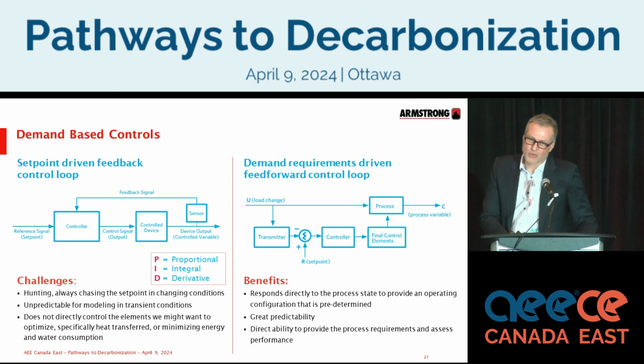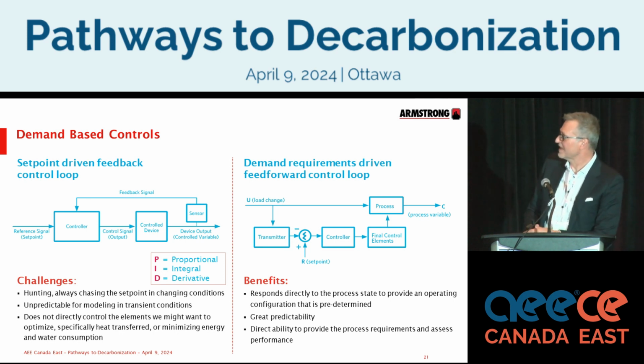Now, how are the controls done? Fundamentally, we are moving away from set point control, PID loops, to demand-based controls. When we talk about demand-based controls, what we're saying is we respond directly to the process state to provide an operating configuration that is predetermined. And I'll get into a bit more detail on what that means in a few slides.